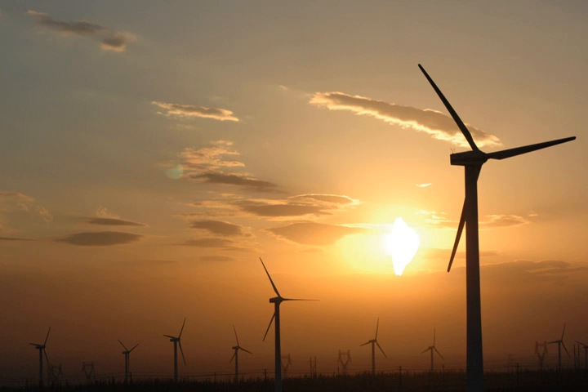Topic: collection and transmission network. In a wind farm, individual turbines are interconnected with a medium voltage, usually 34.5 kV, power collection system and communications network. At a substation, this medium voltage electric current is increased in voltage with a transformer for connection to the high voltage electric power transmission system. A transmission line is required to bring the generated power to, often remote, markets. For an offshore station, this may require a submarine cable. Construction of a new high-voltage line may be too costly for the wind resource alone, but wind sites may take advantage of lines installed for conventionally fueled generation.